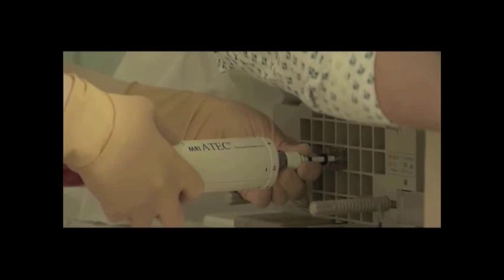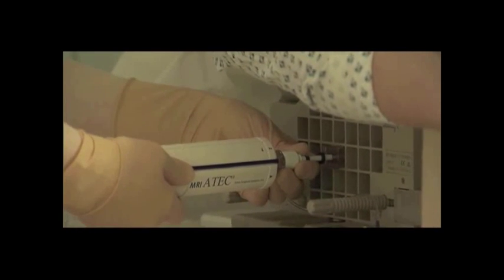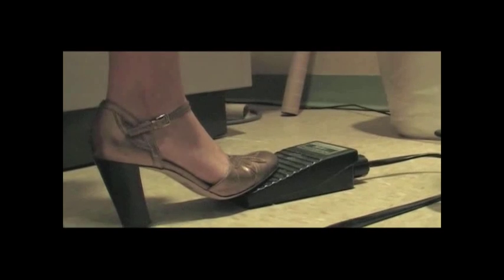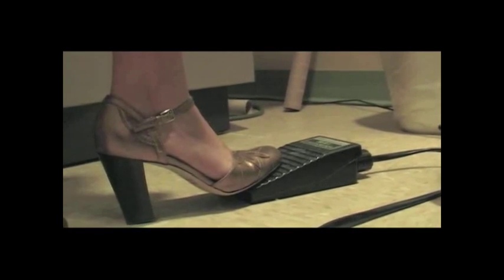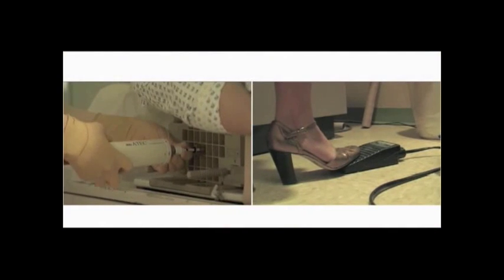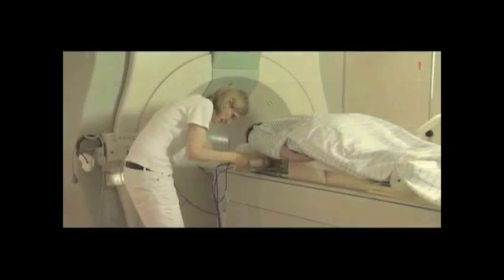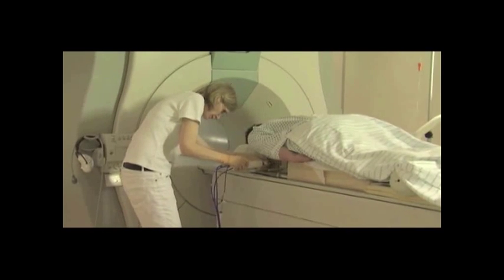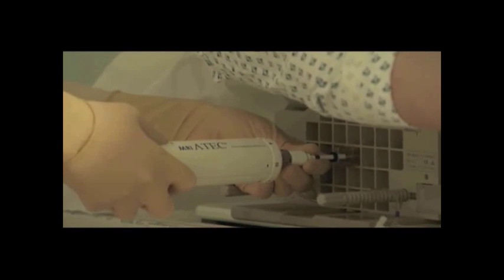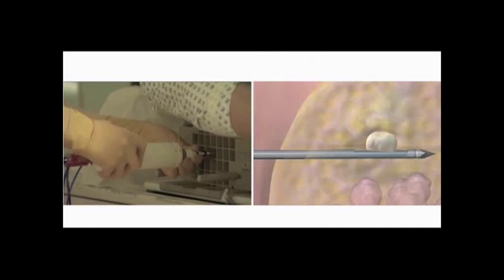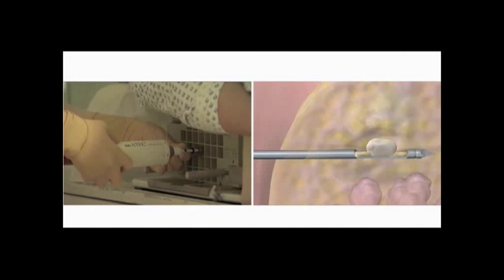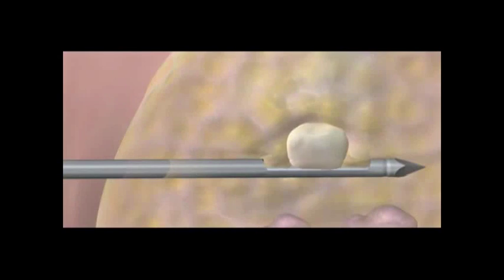Core samples can be taken at any clock position depending on the location of the area of interest. Depress the foot switch to activate the biopsy system and continue to hold the foot switch down throughout the tissue acquisition sequence. Tissue acquisition occurs every 4.5 seconds. A beep indicates the end of one cutting cycle. Manual rotation of the handpiece occurs just after the beep during the resting phase of the biopsy cycle. The ATEC handpiece acquires tissue samples until the foot switch is released when all necessary core samples have been retrieved.